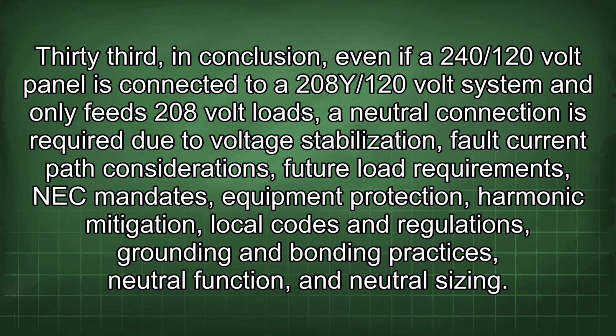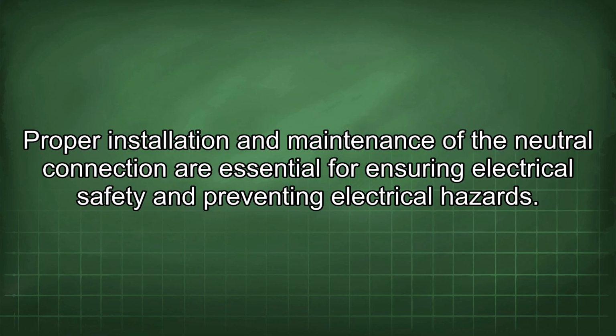33rd, in conclusion, even if a 240/120 volt panel is connected to a 208Y/120 volt system and only feeds 208 volt loads, a neutral connection is required due to voltage stabilization, fault current path considerations, future load requirements, NEC mandates, equipment protection, harmonic mitigation, local codes and regulations, grounding and bonding practices, neutral function, and neutral sizing. Proper installation and maintenance of the neutral connection are essential for ensuring electrical safety and preventing electrical hazards.